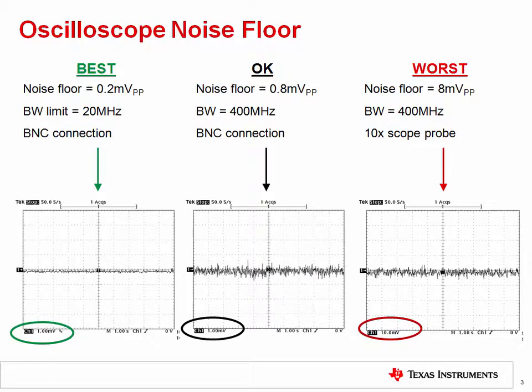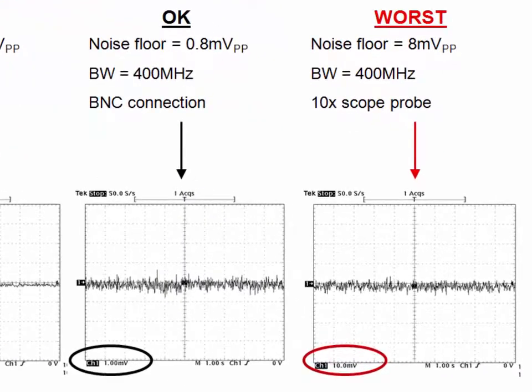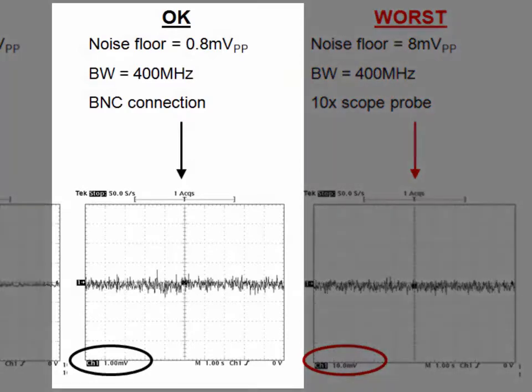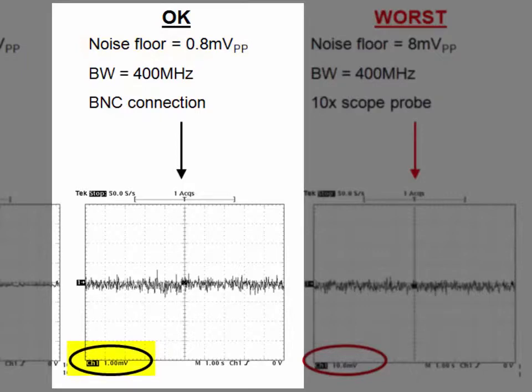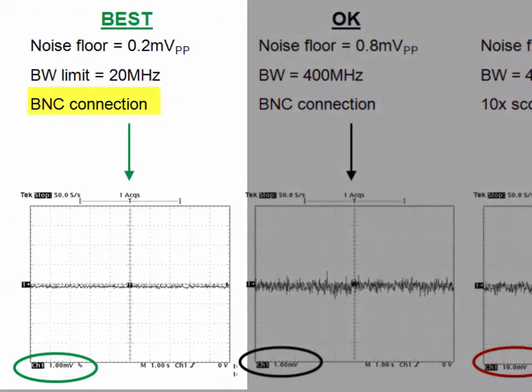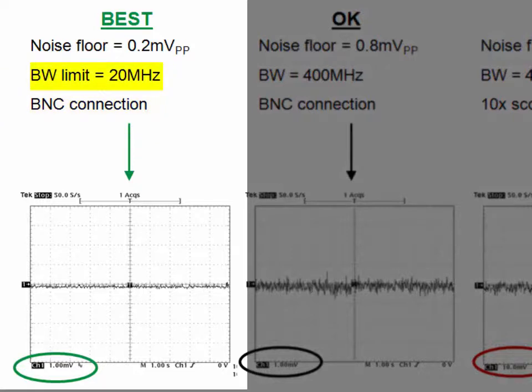Here we show a typical digital oscilloscope measuring its noise floor in three different configurations. The worst configuration, shown on the right, has a noise floor of 8 millivolts peak-to-peak, using a 10x scope probe with the scope bandwidth at the full 400 MHz. Replacing the 10x probe with a direct BNC connection effectively decreases the noise floor by a factor of 10, with the vertical range changing from 10 mV/div to 1 mV/div. The best noise floor occurs when a BNC connection is combined with the bandwidth limiting feature, reducing noise from 0.8 mV to 0.2 mV.